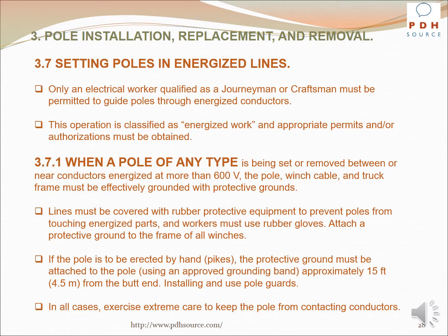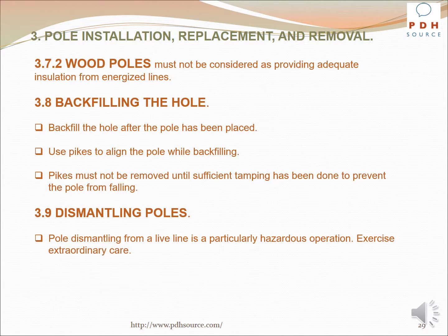Lines must be covered with rubber protective equipment to prevent poles from touching energized parts, and workers must use rubber gloves. Attach a protective ground to the frame of all winches. If the pole is to be erected by hand, pikes, the protective ground must be attached to the pole using an approved grounding band approximately 15 feet from the butt end. Install and use pole guards. In all cases, exercise extreme care to keep the poles from contacting conductors. Wood poles must not be considered as providing adequate insulation from energized lines.